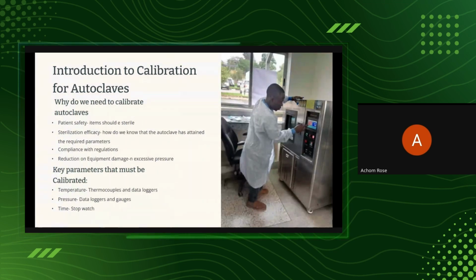So when you are doing the calibration of autoclaves, what are the key parameters that we should consider? First is the temperature. Okay, remember, for sterilization to take place, we need to attain a certain temperature and pressure, and then we perform this stage at a given set time. So the key aspects that we look at are temperature, pressure, and time. In temperature, you can have about two types of equipment that you use to perform the calibration of the temperature parameter. One, we have the thermocouples.